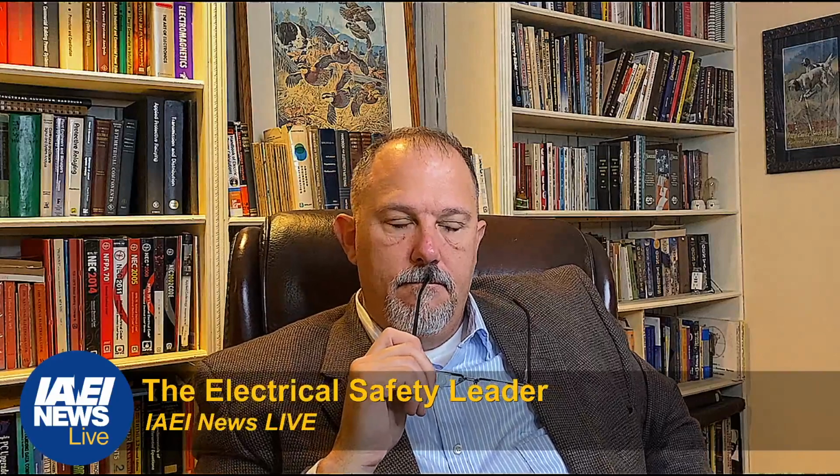They said use of non-contact, and it's not proximity test instruments, it's capacitive test instruments. That's what you're doing. It's a capacitor type of thing. They removed the measurement of voltage on the secondary side of a low voltage transformer. Now, we can have an argument or a debate about that, but they focused this in on just using a capacitive, non-contact, capacitive test instrument.